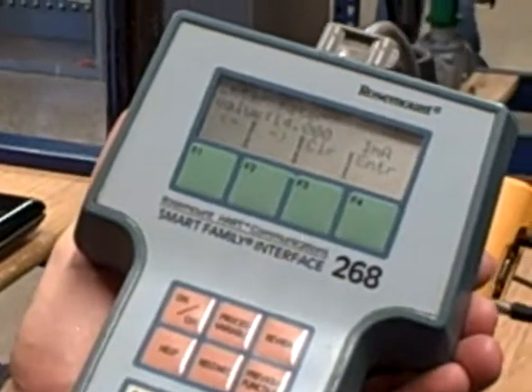And we get 4.00, 4.01. And it says enter the meter value. It wants me to type in what the meter actually tells me. And the meter is actually telling me 4, so there's no need to trim this. I can hit the enter button and proceed.